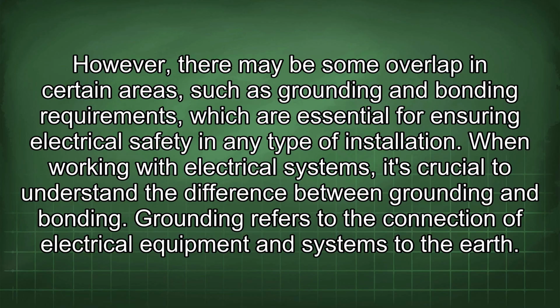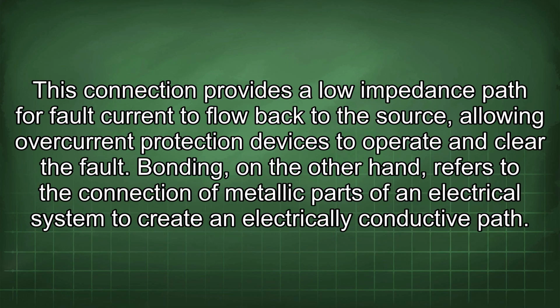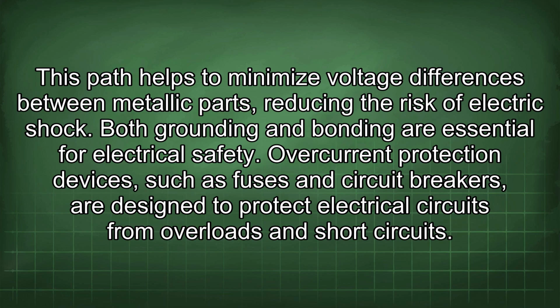When working with electrical systems, it's crucial to understand the difference between grounding and bonding. Grounding refers to the connection of electrical equipment and systems to the earth. This connection provides a low impedance path for fault current to flow back to the source, allowing overcurrent protection devices to operate and clear the fault. Bonding, on the other hand, refers to the connection of metallic parts of an electrical system to create an electrically conductive path. This path helps to minimize voltage differences between metallic parts, reducing the risk of electric shock. Both grounding and bonding are essential for electrical safety.